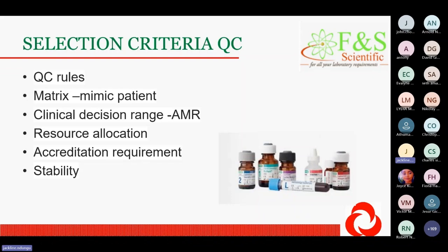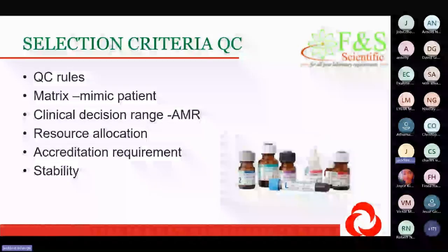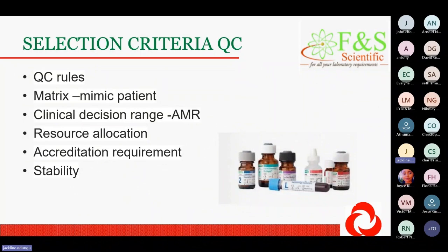When I say clinical decision range, when you have your analytical measurable range, and I mean this because we may have people who have not been so much in quality, once your instrument is supposed to be linear up to this level, you want to capture the biggest range, on the lowest range and on the highest range. For example, if you are doing a chemistry test that has an analytical range of, let's say, 10 to 1,000, I'm just giving an example, your QC should capture around that 10 minus and the 1,000 plus, so that you capture what you're dealing with.